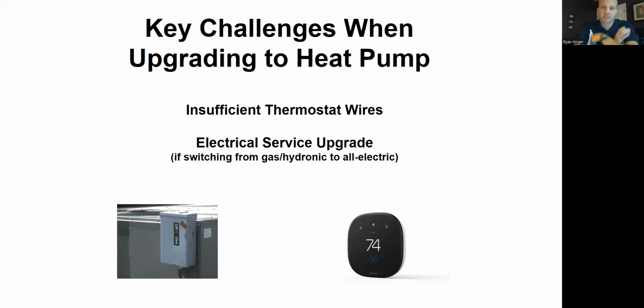So we're making these retrofits from cooling only small split systems to heat pump versions of them. If you're going from a gas furnace and AC to a gas furnace and heat pump, or it could be oil furnace and AC, oil furnace and heat pump, although I don't think a lot of commercial buildings have oil furnaces at this point, but maybe some do, or propane. If you're going to do one of those things, the only thing you really have to do differently is the thermostat wiring.